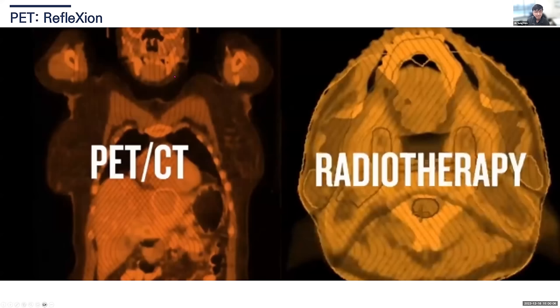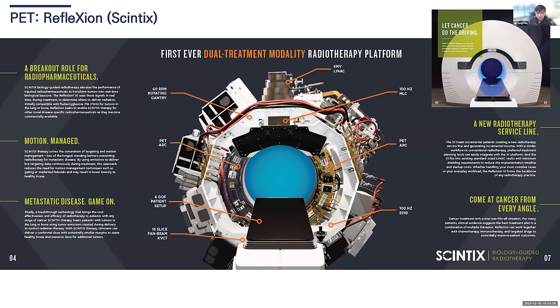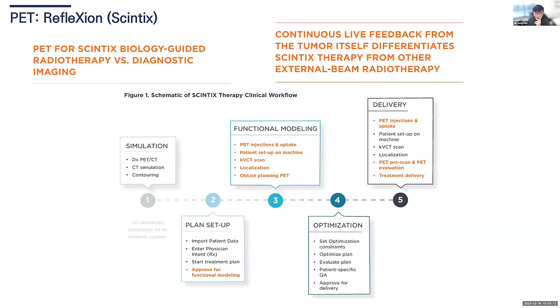Finally, there is another X-ray system using a PET detector — the RefleXion system. This is not available in Asia at the moment; I believe they are trying to get FDA clearance and have already started treatment in the US. The system has a 6 MV linac and 16-slice fan beam CT. They can get in-beam PET imaging during treatment, allowing higher dose delivery to the tumor based on that imaging.